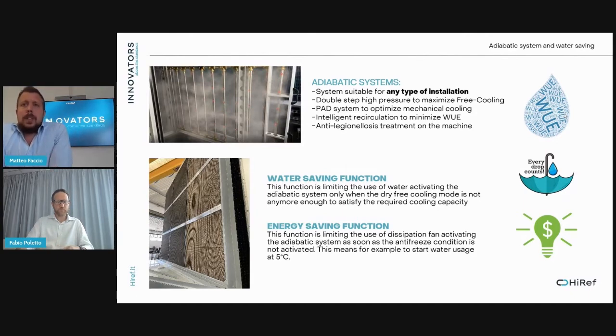There are many different systems to use adiabatic technology. We can provide two. The most used one is to spray water directly into the airflow stream at medium-low pressure. Yes, and the other possibility is to use a pad system. So it's made of cardboard or other material that gets completely wet, and the air going through this element gets the benefit of the evaporative effect. You say that water is a primary resource, so we need to find a way to manage it in the most convenient way, at least.